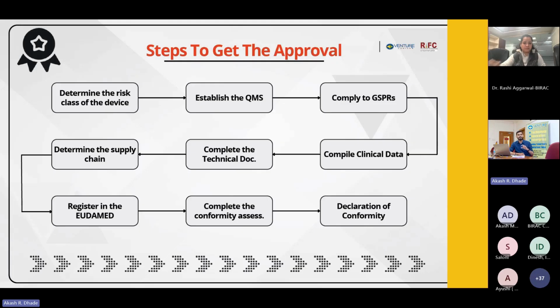And in that text, there is a section, Annex 1, which is called General Safety and Performance Requirements. There are around 23 requirements divided for different aspects of the medical device life cycle. These 23 are also divided into sub-clauses. So you should make a list, an Excel sheet or a format wherein you enlist all those requirements. You state its applicability for your device. You provide the reference standard and provide the evidence documents. So that is how you generate the GSPR, and that document should be drafted.